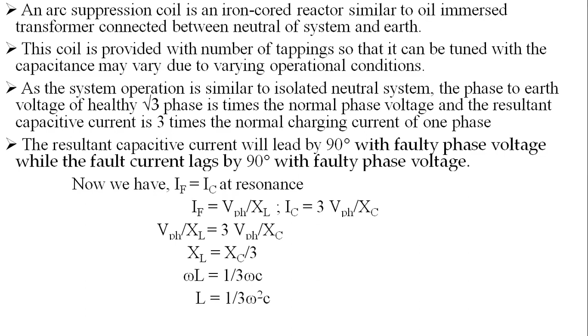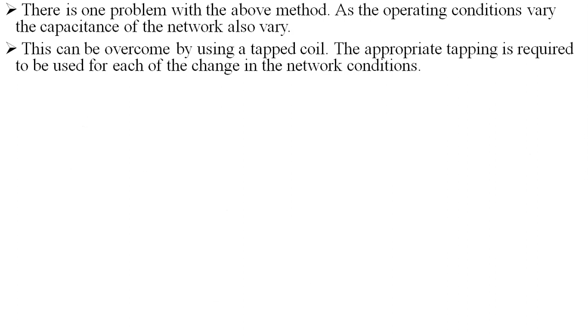There is one problem with the above method. As the operating conditions vary, the capacitance of the network also varies, and this can be overcome by using a tapped coil. The appropriate tapping is required to be used for each change in the network conditions. The current rating of the coil is given by I fault equals 3 times the phase voltage by the capacitive reactance. And the time rating of the coil used in systems where earth faults are located and removed is around 10 minutes.